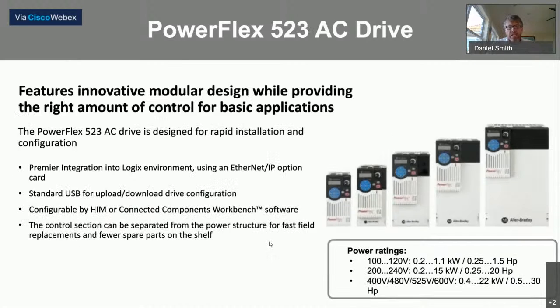The 523 drive has a premier integration platform. Rockwell has designed an AOP that you can download to pull all the tags and the Logix and get all that information needed. The 520 series drive is the smallest in class of anybody else's drives. It also has the highest temperature rating. Straight out of the box, all the 520 series drives are rated to 124 degrees Fahrenheit, I believe.